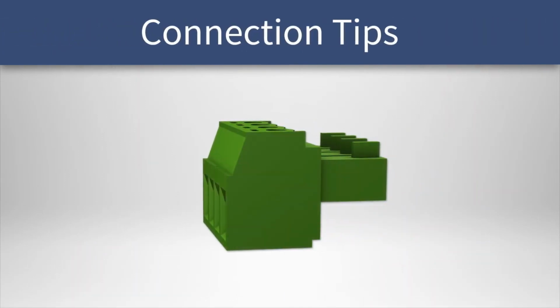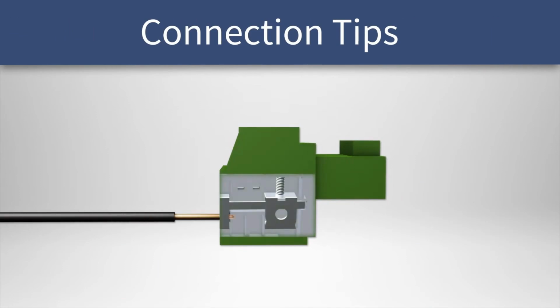When attaching the wires to the terminal block, it is important to ensure a secure connection between the clamp in the block and the bare wire. If there is insulation between the wire and the clamp, it will not work properly. The insulation should be stripped to expose enough wire for a good electrical connection.